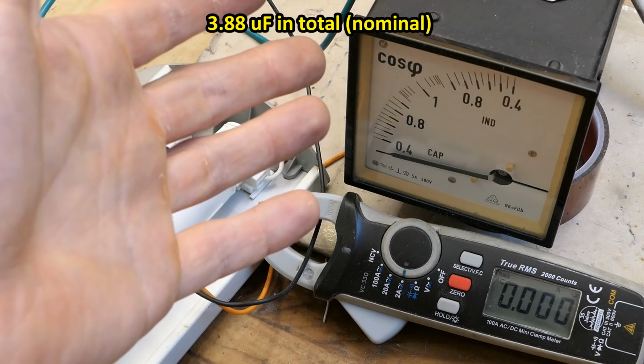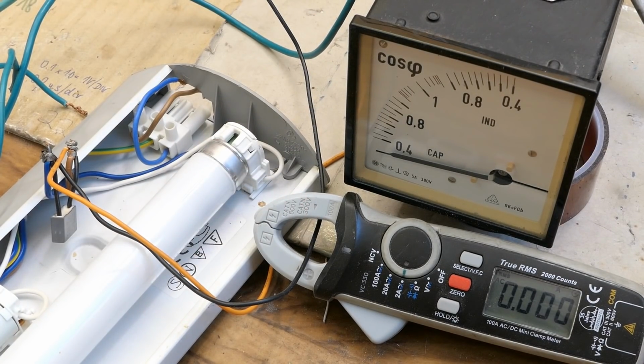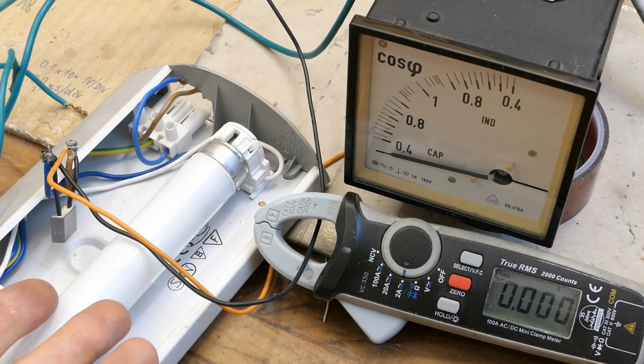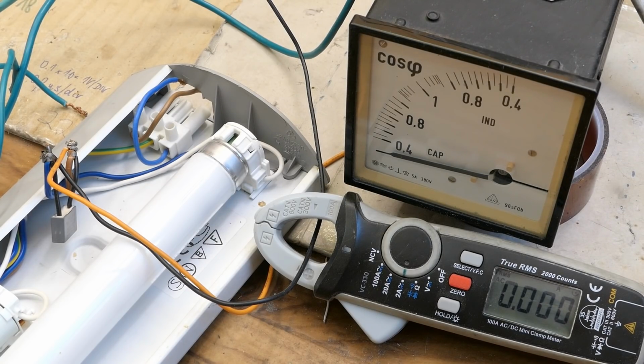So that's the power factor meter in operation and how it can be used to find the right compensation to minimize the current draw of an inductive or capacitive load. The fluorescent fixture with no compensation is drawing over 300 milliamps, and with the right compensation just 110 or 120 milliamps. Of course, some fluorescent fixtures have a built-in compensation capacitor, but some of them have none.